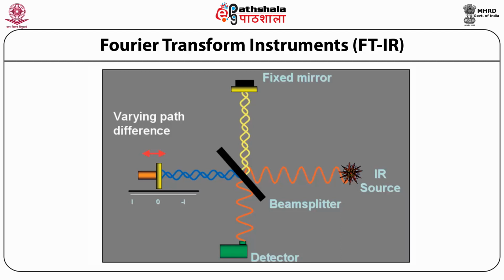The IR beam next passes through the sample, where some energy is absorbed and some is transmitted. The transmitted portion reaches the detector, which records the total intensity. The raw detector response yields an interferogram. The interference pattern contains information about all wavelengths being transmitted at once, which is a function of the source, beam splitter, mirror and sample.